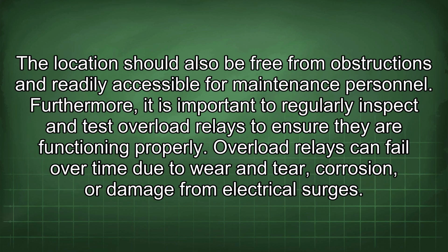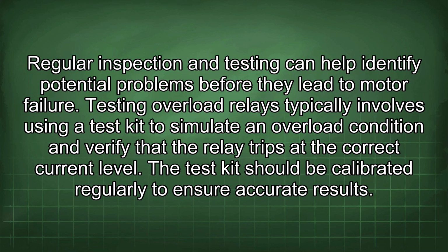The location should also be free from obstructions and readily accessible for maintenance personnel. Furthermore, it is important to regularly inspect and test overload relays to ensure they are functioning properly. Overload relays can fail over time due to wear and tear, corrosion, or damage from electrical surges. Regular inspection and testing can help identify potential problems before they lead to motor failure.